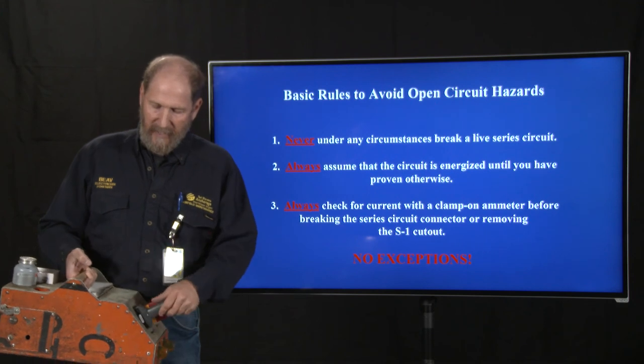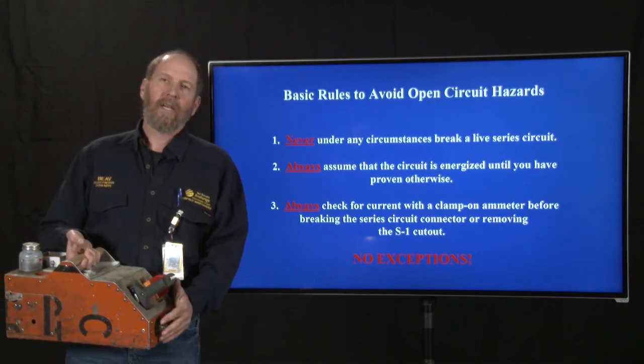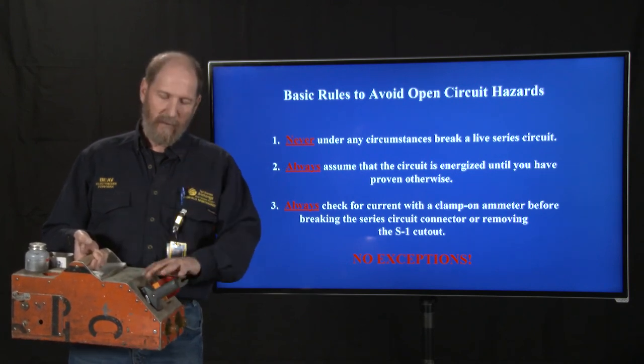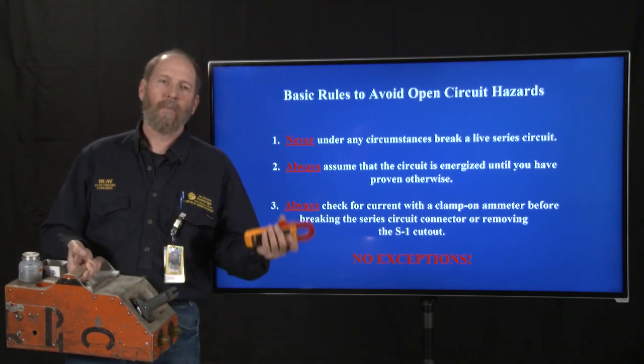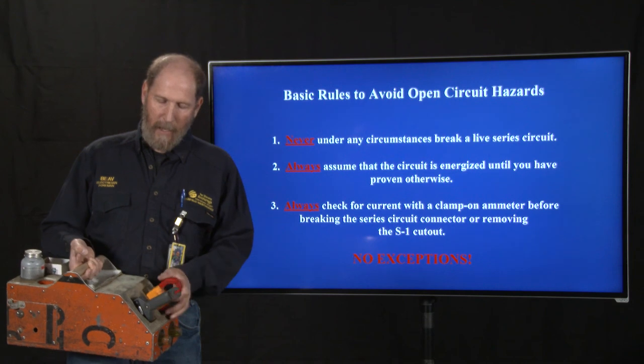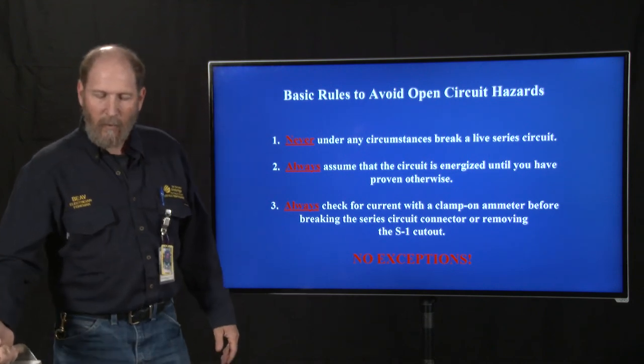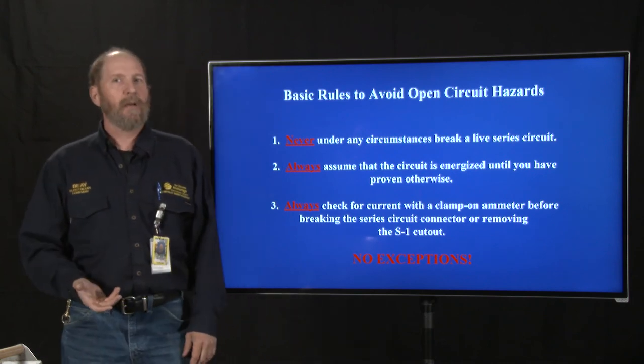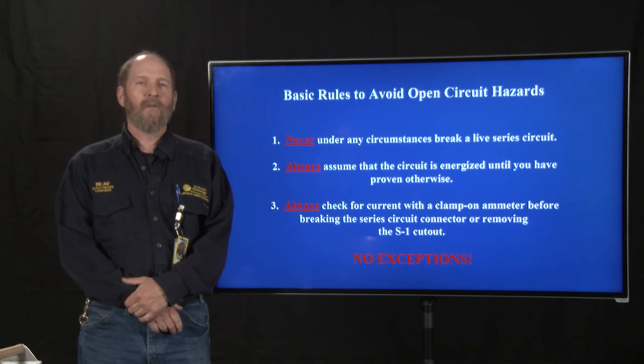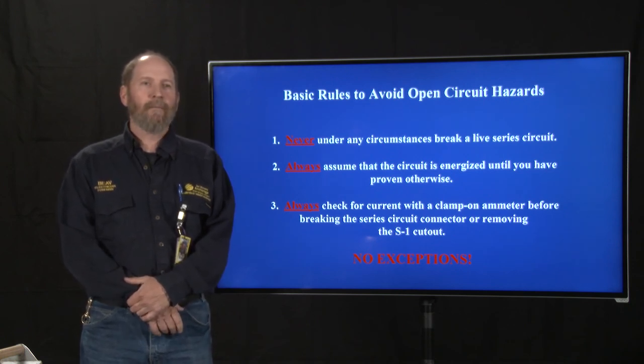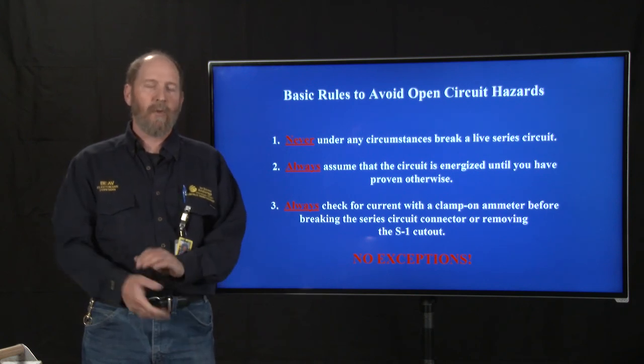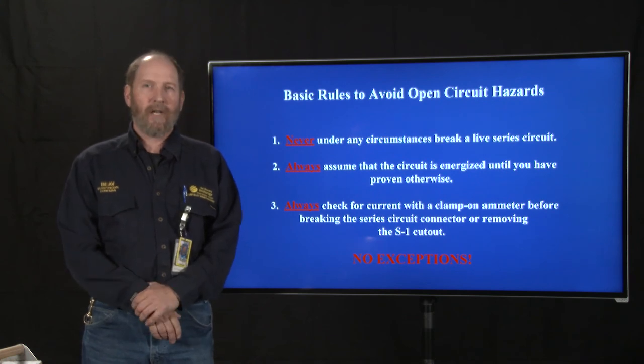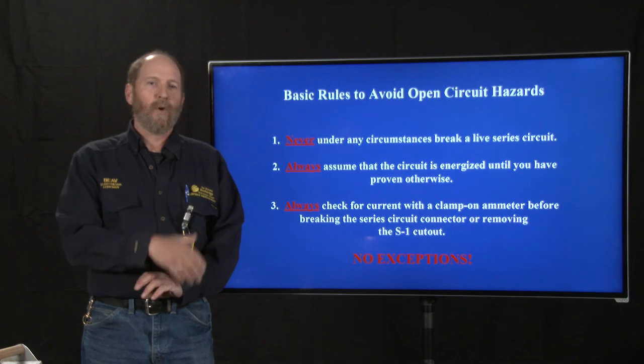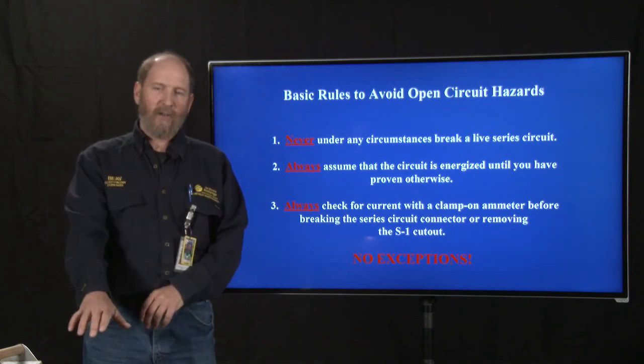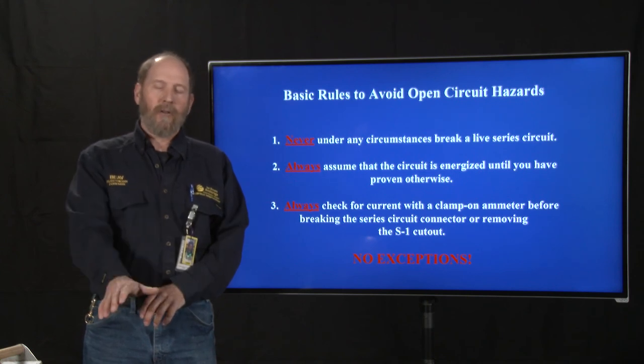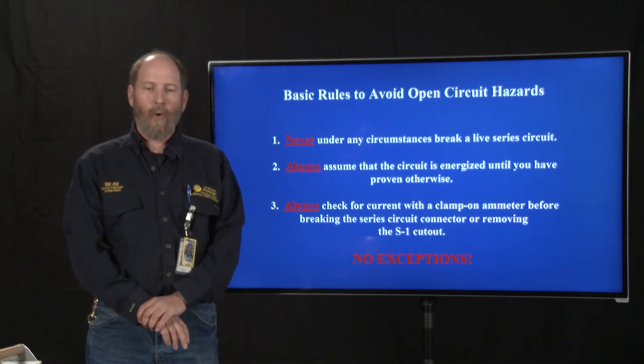The idea is that every time we need to get into a live circuit, we will use these tools. And so that's the perfect place to keep our safety equipment. There is no excuse to not whip out the ammeter and clamp on if it's right there. Now, I do know of one story of a gentleman who was working on an airfield. He was issued a clamp-on ammeter. I assume that maybe it was in his truck. The truck was more than 50 feet away from where he was working. His partner went to get the truck to move it closer to where he was working, and when his partner came back, the gentleman had cut into a live wire and he was dead. He had not checked with the ammeter. The ammeter was probably in the truck. So having your safety tool right with you is very important. You should clamp on every time before you cut into or open up a constant current system.